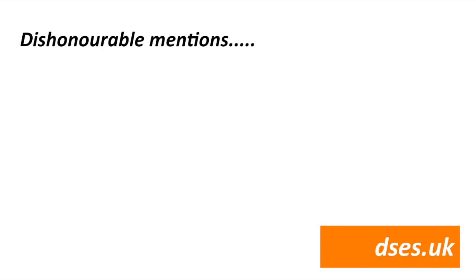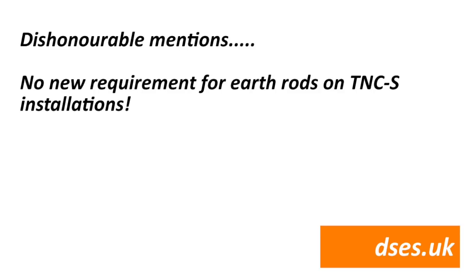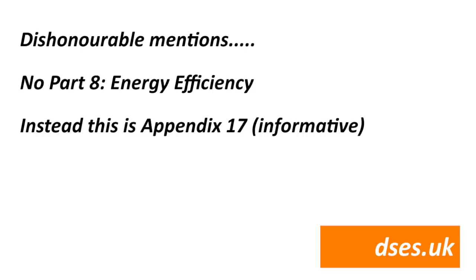You may have heard rumours about earth spikes being required for TNCS installations — thankfully that was dropped. There is no new requirement for earth rods in the 18th edition. It was such a ridiculous suggestion I honestly wonder if it was mooted as a red herring to detract from the other changes and give us all something to shout about. Originally there was also going to be a new Part 8 on energy efficiency, but this has instead been rolled into a new informative appendix — Appendix 17 — so 18th edition still has seven parts but now 17 appendices, with only Appendix 1 being normative. You can expect to see Appendix 17 become Part 8 when IET and BSI feel like sending us all new books. Appendix 17 covers energy efficiency, lighting controls and voltage drop versus cable size.